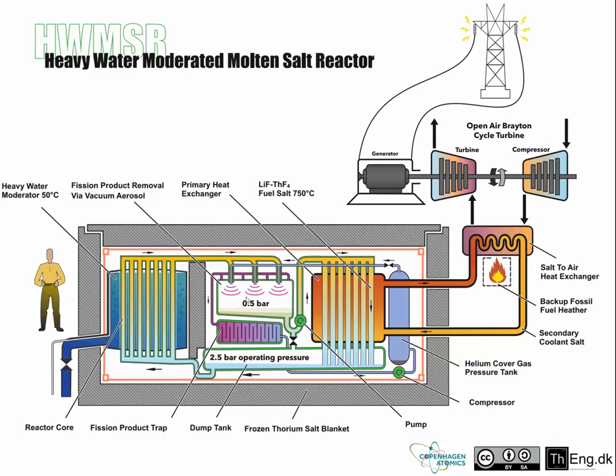Once the salt is heated up inside the reactor core, it flows into the vacuum chamber, where we believe we can remove 25 to 50% of the fission products by helium spraying. The helium leaves this vacuum chamber, passes through a filter that extracts most of the xenon and krypton and other species of gaseous fluoride. Then mostly helium is left over and sent into a compressor and stored in a compressed helium tank. A valve can slowly release the helium at the speed we need back into the vacuum chamber again, completing the helium loop.